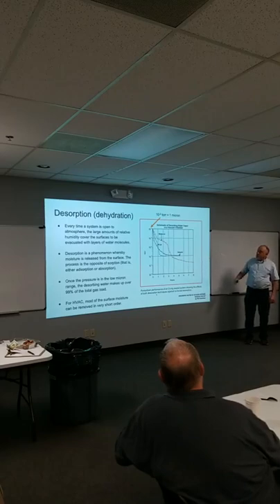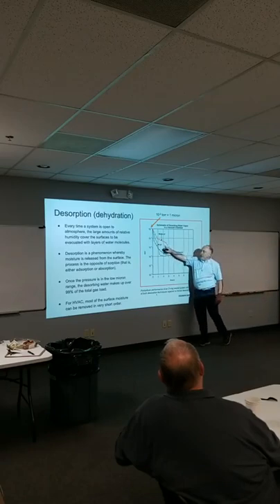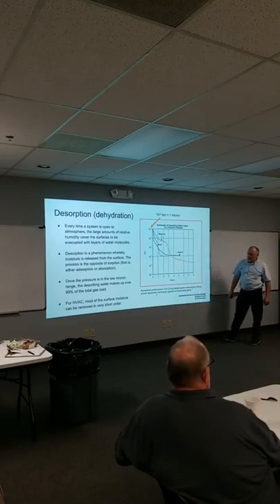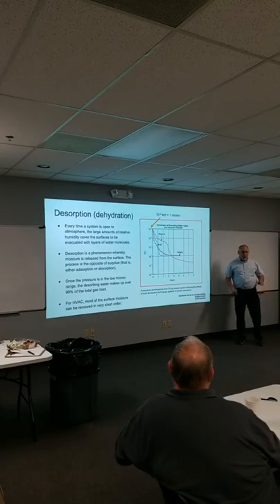And so what we're showing here, this is 10 to the minus 3, this is 1 micron, but when you get into really deep vacuums, what they're doing here is removing moisture by heat or by ultraviolet light, right? And it's just showing the rate of desorption on the graph here. But once the pressure is in the low micron range, here's what I want you to understand: once we're down to 500 microns, 99% of the load in the system is moisture.